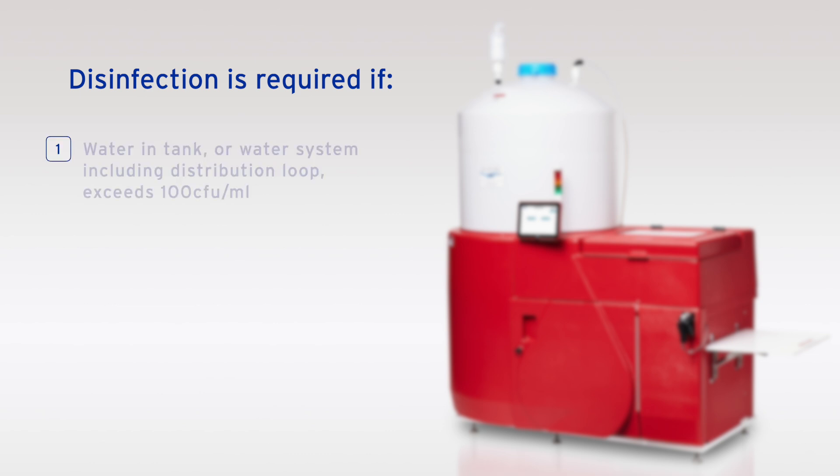Disinfection is required if: 1. Water in tank or water system, including distribution loop, exceeds 100 CFUs per milliliter. 2. Water is left in mixer with no acid for 4 hours or more.